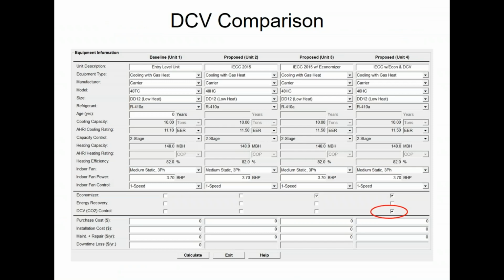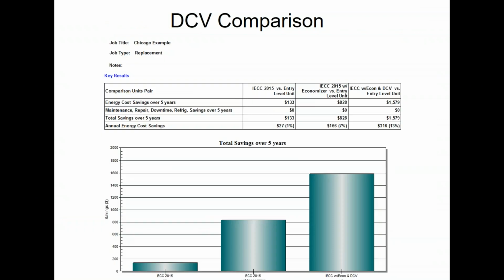If we look at that same software tool and we add a 4th column for a code compliant unit with an economizer and DCV, just for argument's sake, then that gives us, instead of 7% just for the economizer, up to 13% for the economizer with the DCV. So there is some real energy savings for a fairly inexpensive sensor.